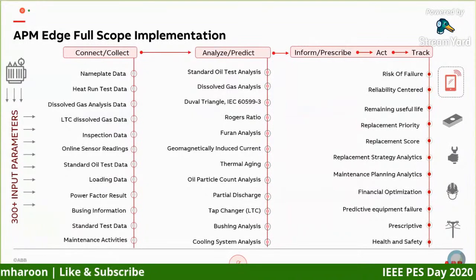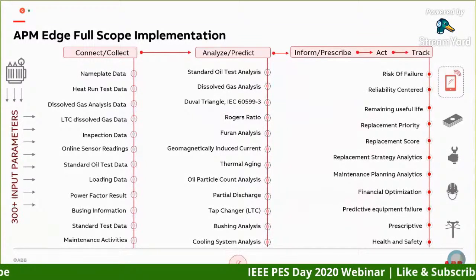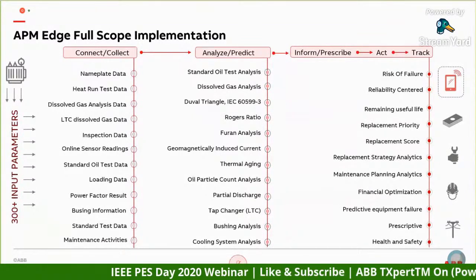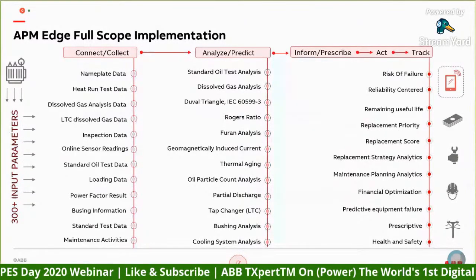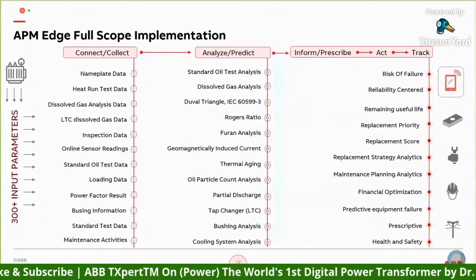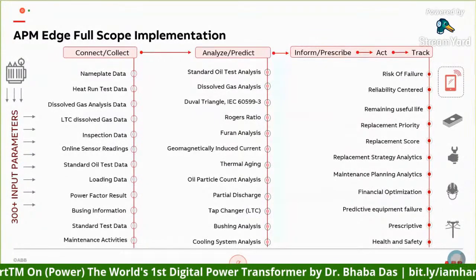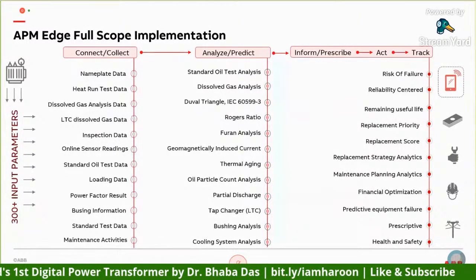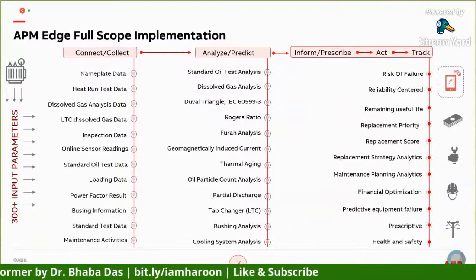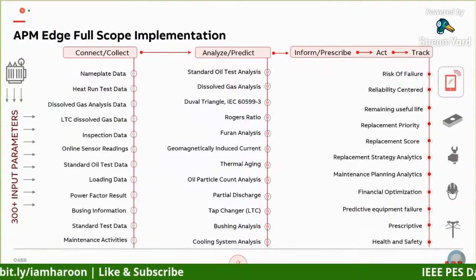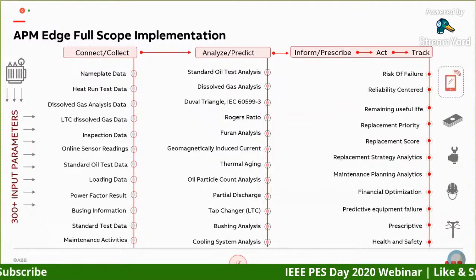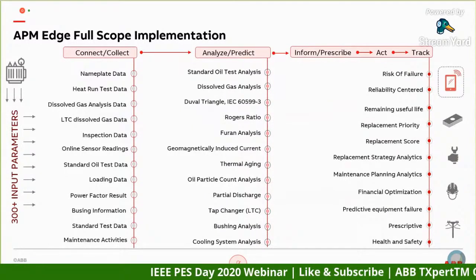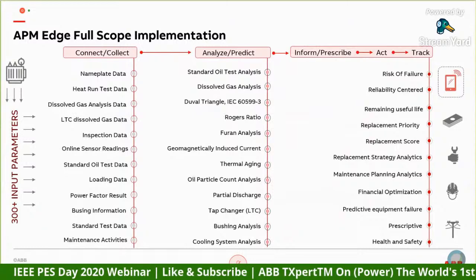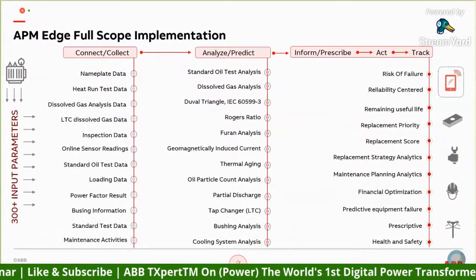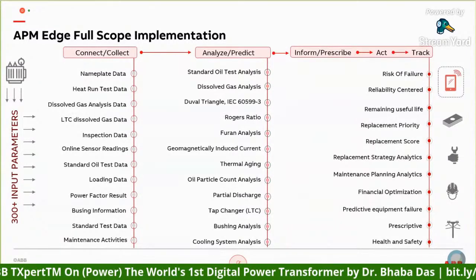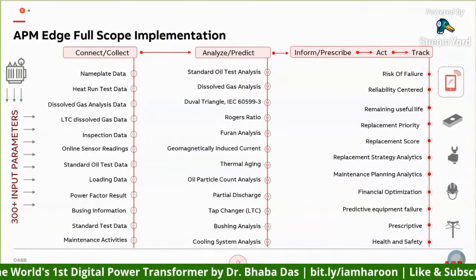But if you give this model more and more data, the whole digital transformer ecosystem will start giving you much better results. So you can see we do a lot of different algorithms: DGA, furan, GIC, thermal, particle count, PD, bushing analysis, OLTC analysis, cooling analysis, and based on that, we give you the risk of failure of the transformer. We tell you the remaining useful life of the paper, the replacement priority, and the replacement score.